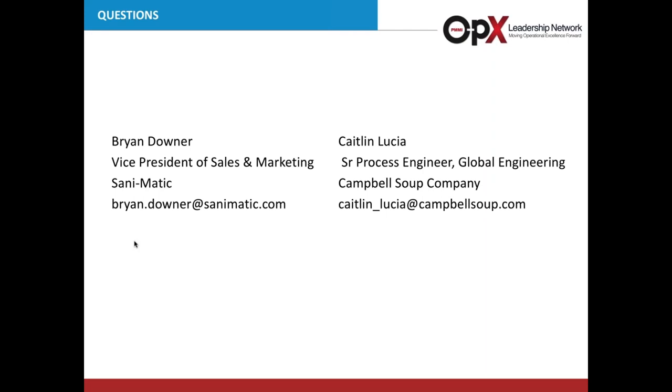Caitlin, if I want to swap out my single-tank system with a multi-tank reuse system, what do I need to consider? The two most obvious factors are space and cost — you have to justify the multi-tank system and find a home for it. Then consider allergens: is it possible for you to cross or reuse your fluids? One thing people usually don't think about is that because you're reusing fluids, some soil will end up back in your CIP system — you have to periodically clean your CIP tanks as well to prevent buildup. Those are the big three when swapping from single-tank to multi-tank.